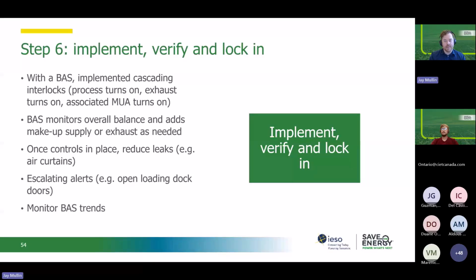Another interesting piece that they put in, in terms of locking in these changes and savings, is they implemented a system of escalating alerts. So, for instance, if a loading bay door was left open longer than it should be, then the person in the loading bay was notified, and if it was left open another hour or so, then the shift supervisor was notified. And if it was left open even longer, after a certain threshold, the plant manager was notified, which was really good in terms of an energy saving measure and maintaining the pressure balance in the facility, because no one wants to be the reason why the plant manager gets notified of something. So it really helped people stay on top of things.